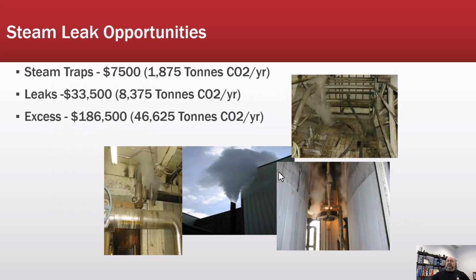So we took a look, just in a walk through the plant, we found steam traps. Now, on average, if you don't have a steam trap plant practice in place, expect about 10% of your steam traps will fail a year. That is a rule of thumb that we applied in the 1990s and still exists today. So the steam traps that we identified came up to about $7,500, or almost 1,900 tons of CO2 per year. Leaks, just leaks like this one here on the left, and then this one here, which is a steam hose that was just left sitting there. When you get this many acres, you're going to have stuff like this. That came out to 33,000 or 8,400 tons of CO2 per year.